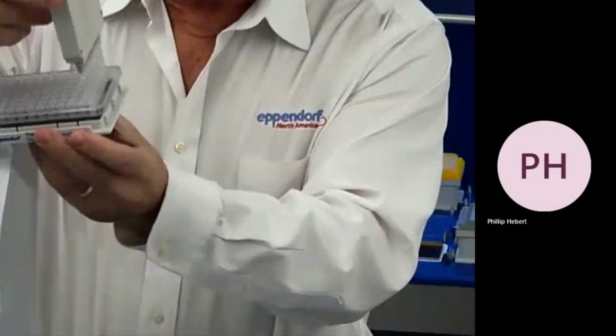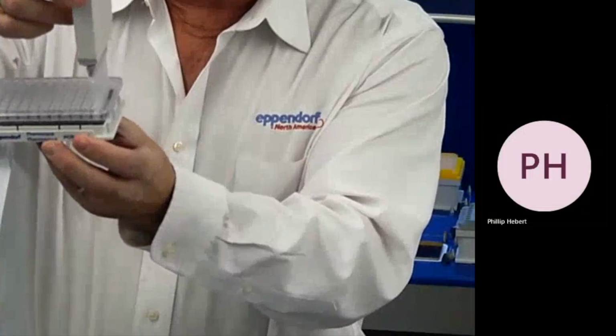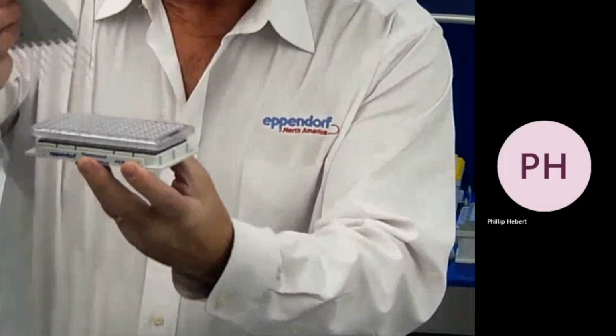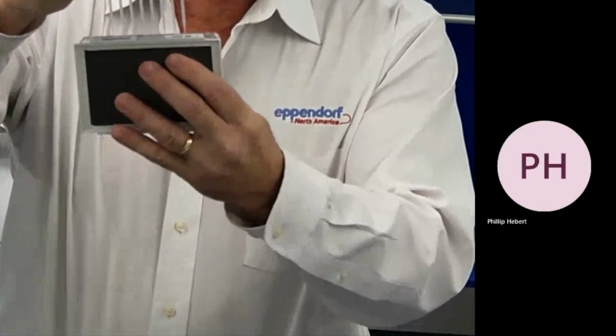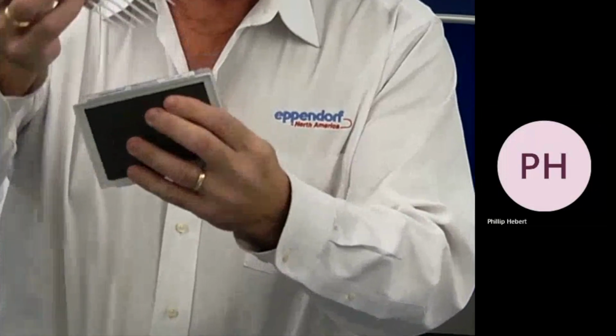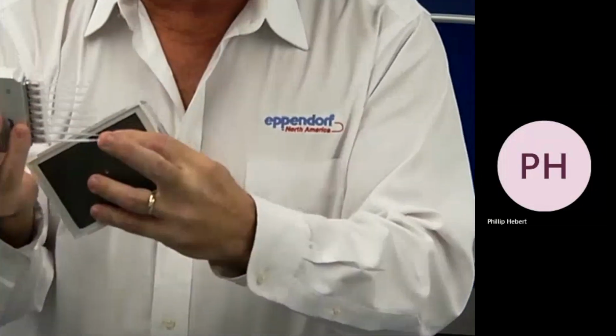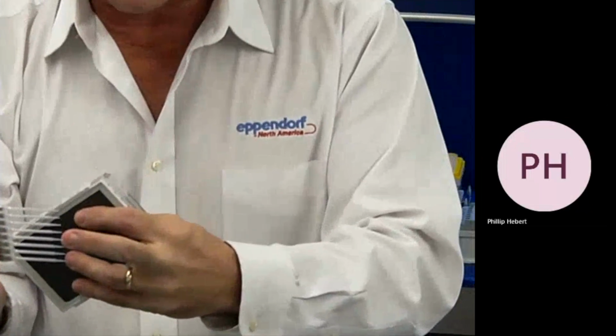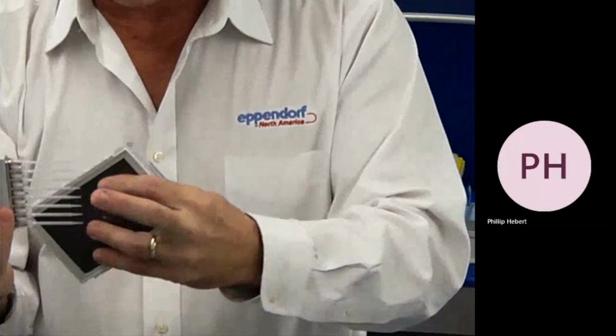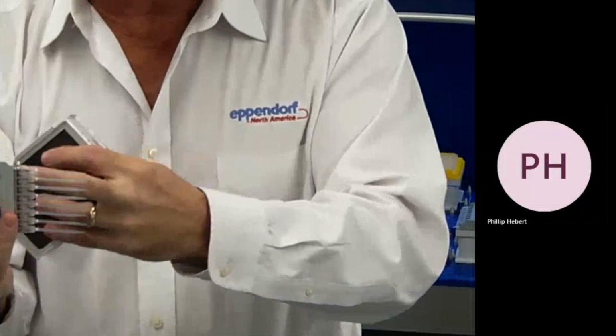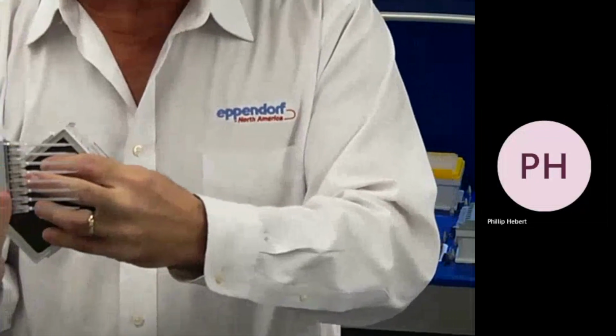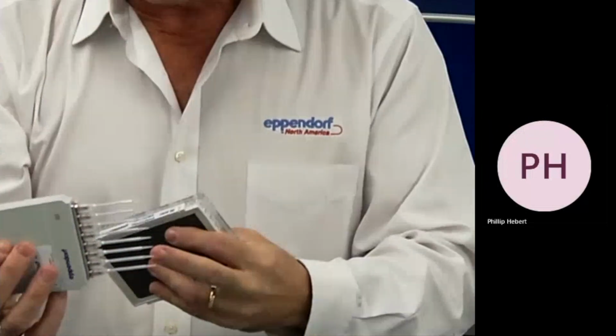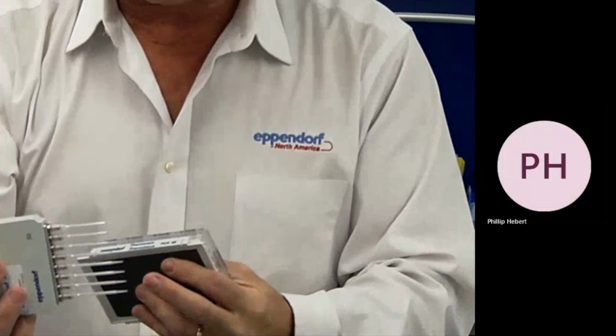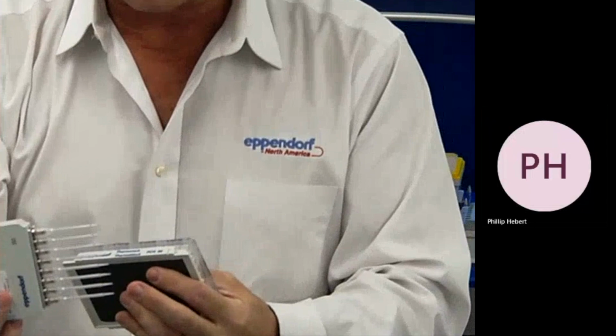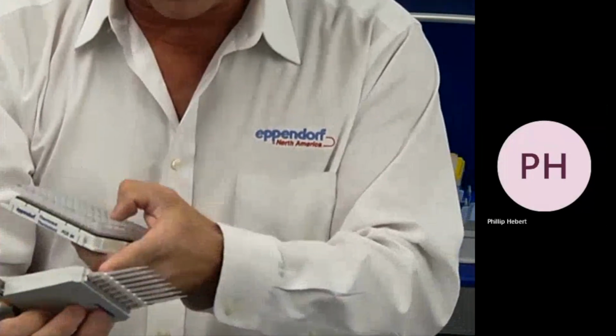So the machine goes into the well. Our machine can rotate a little bit if the tips really have to line up perfectly. When you attach tips, the more tips you have, the more likely that one or more of the tips is going to be not seated quite as deeply as all the others. That is just a fact of life. Now when you attach 96 tips, you have flexion of the plate that you're aspirating from, so the tips will not always seat perfectly.